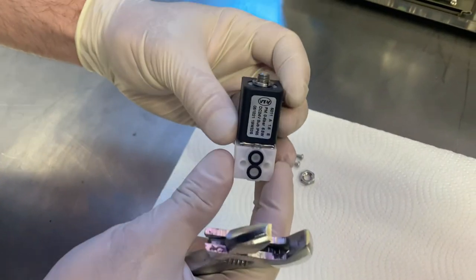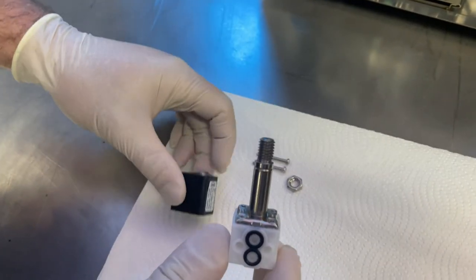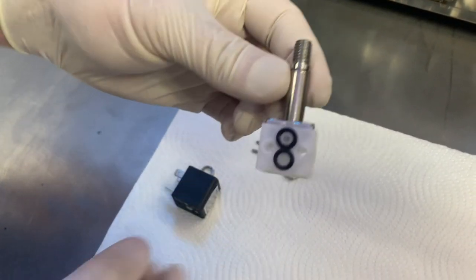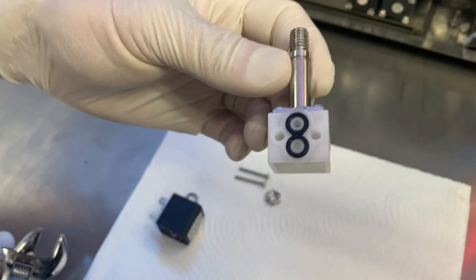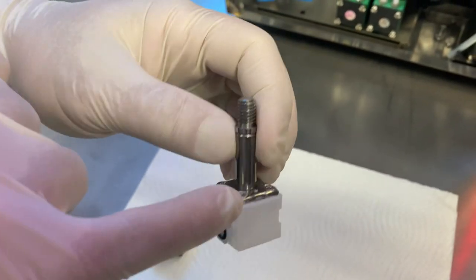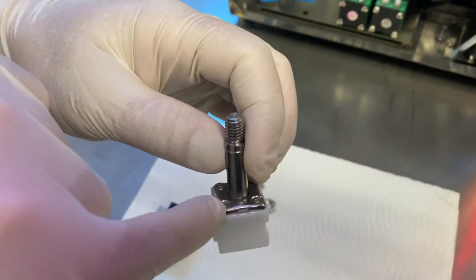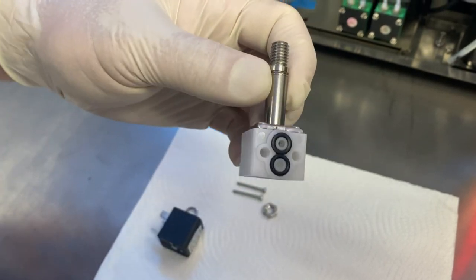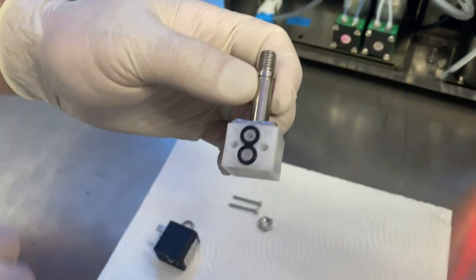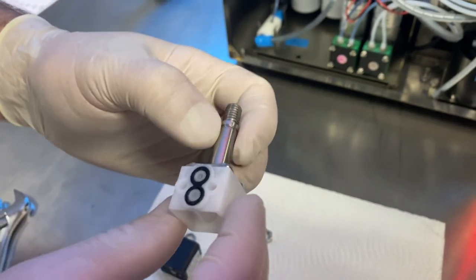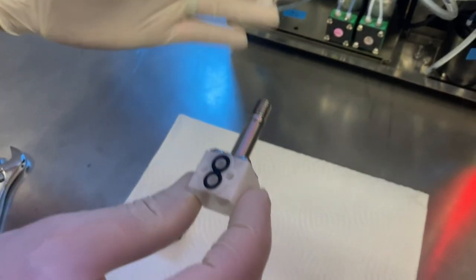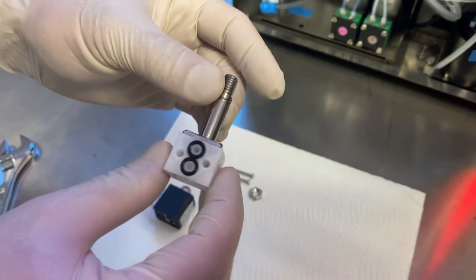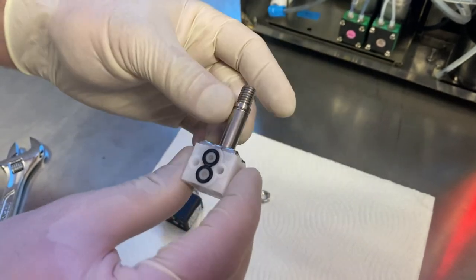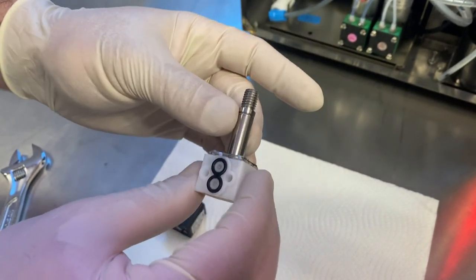We're just gonna loosen this nut on top and we can slide the plunger housing assembly out of the solenoid. So we're just gonna take this off really quick. Same exact torque driver that we used for valve six, T10, same size. Again, everything else is identical. So the only difference between this and valve six is we don't have an extra direction of flow out the top here, and the plunger subsequently is a little bit different.